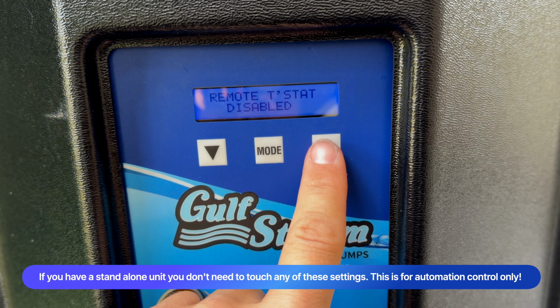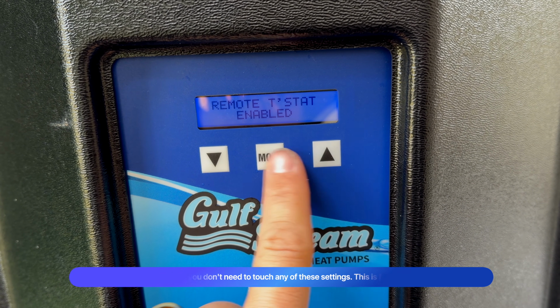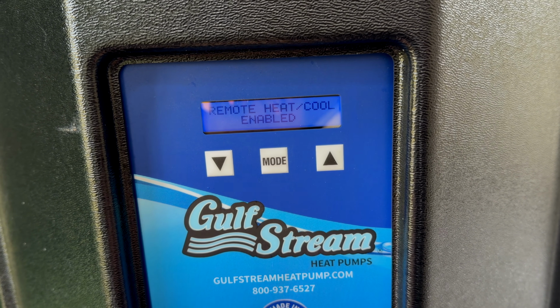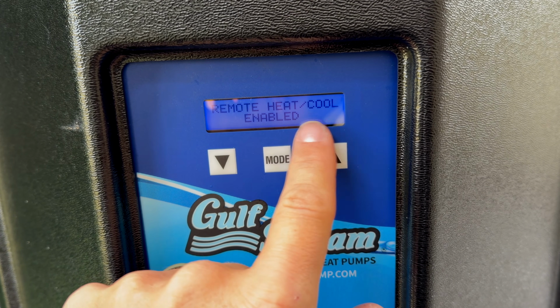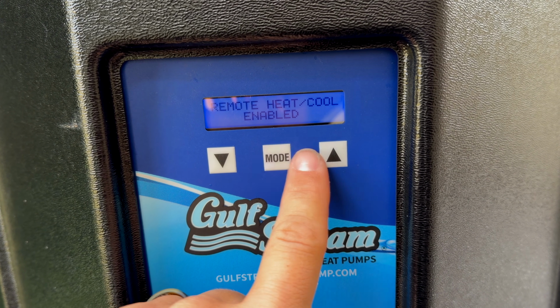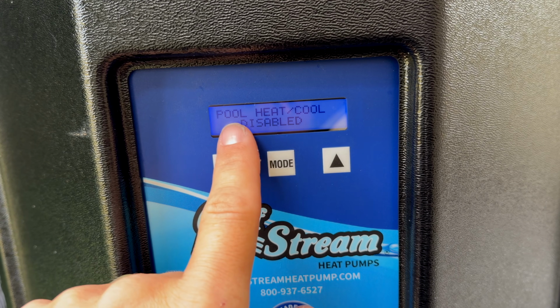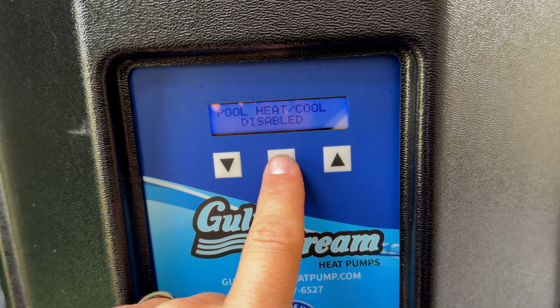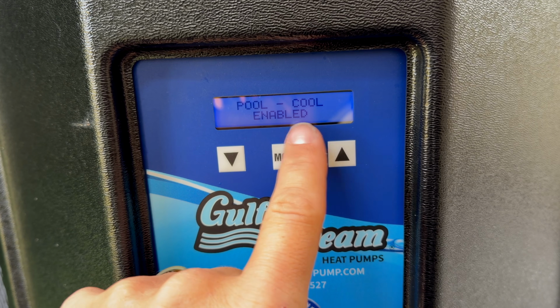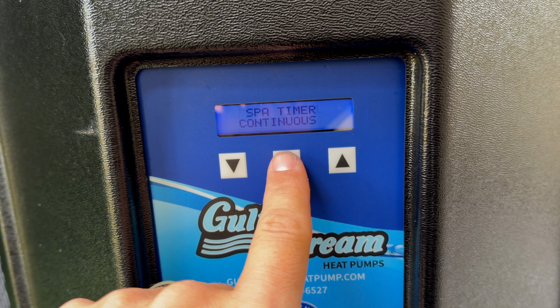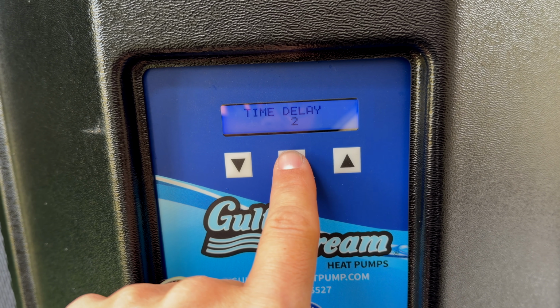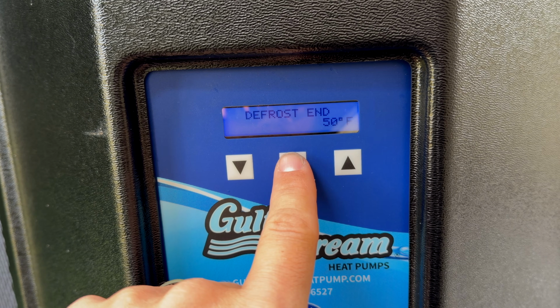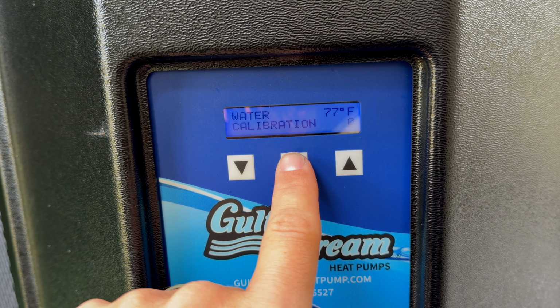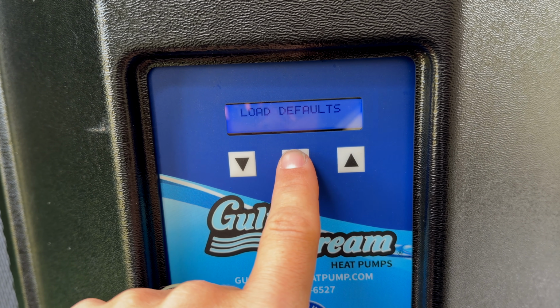You want remote T-stat enabled, so you just make the adjustment with the up or down arrow, and then click mode to go to the next one. We want remote heat cool also enabled. We want pool heat cool disabled. We want pool cool enabled. And that's it. Those are the 3 main ones you got to make sure are set properly to have the automation control the heat pump.